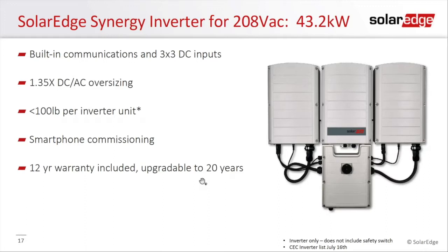In terms of installation, it's a very easy inverter to install because it is modular and less than 100 pounds per inverter engine. As you can see, it's really the 14.4 kilowatt inverter times 3, with one pretty unique change: we eliminated the display. So we now use a SolarEdge application called SetApp, and you would use your smartphone with that application to set up the inverter. First thing it does is download the latest firmware, so you're always operating from the latest firmware. Then you use your smartphone and a very easy interface to complete the commissioning of the site. As with all SolarEdge inverters, it comes with a standard 12-year warranty that can be upgraded to 20 years for a low cost.